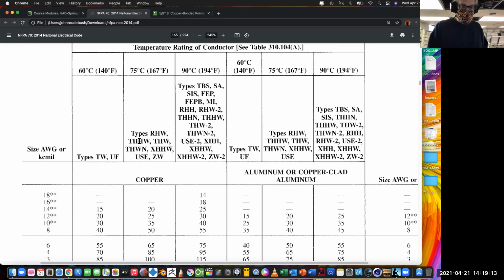If we look over here, we see THHW. That cable is only rated for 75. Or THWN, that cable is only rated for 75 terminations. That means that cable can get up to 167 degrees Fahrenheit, which is much hotter than the water that you take a shower in. The water that you take a shower in is about 120 when you have it turned all the way up. It can be pretty hot, but that shows you it doesn't take a whole lot more. But 194, yeah, that'll cook you.